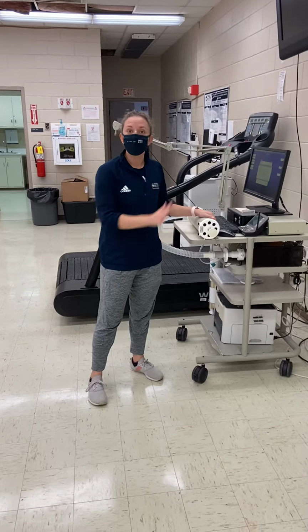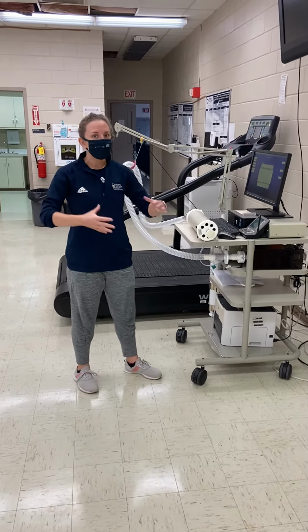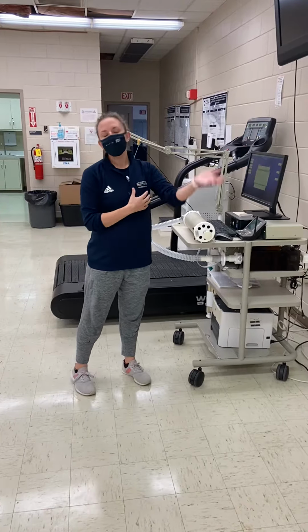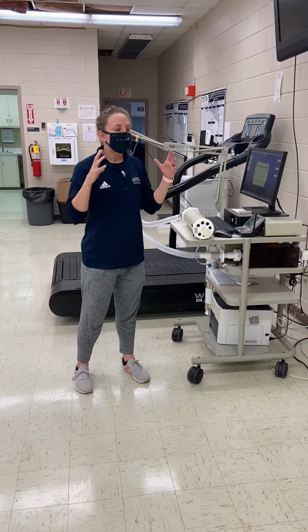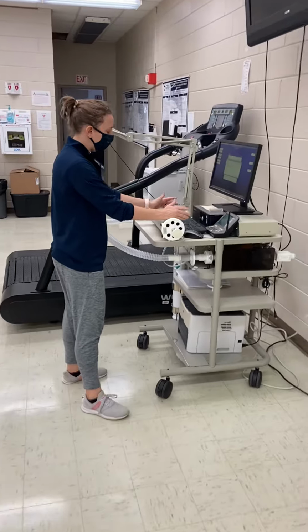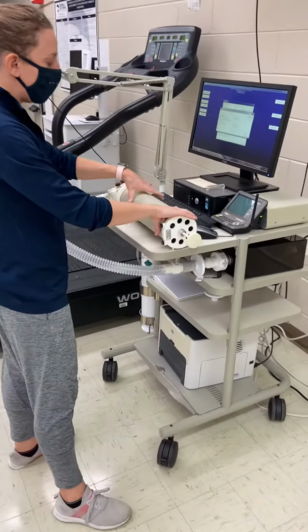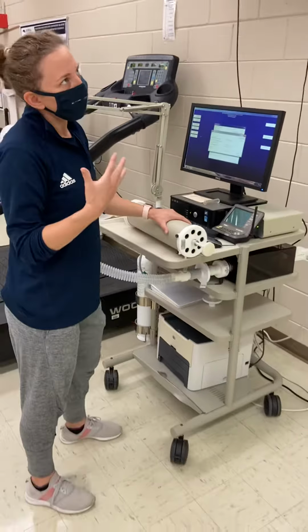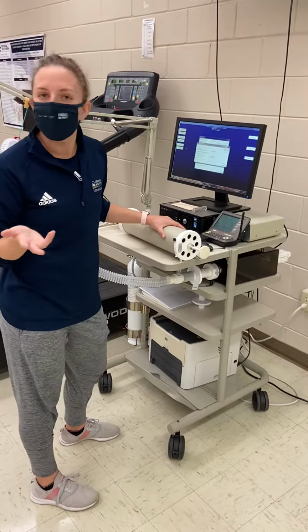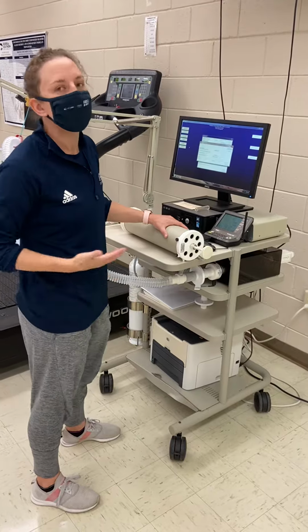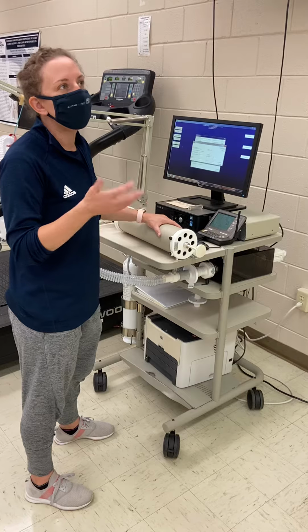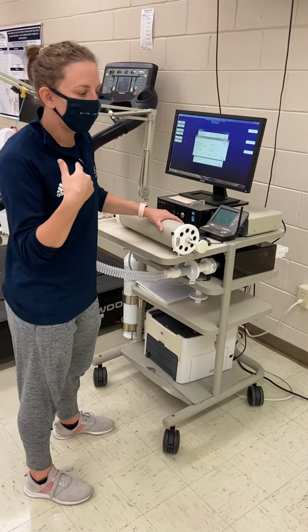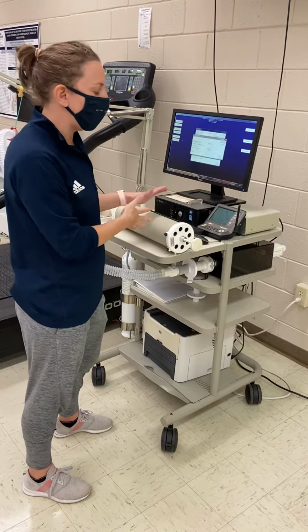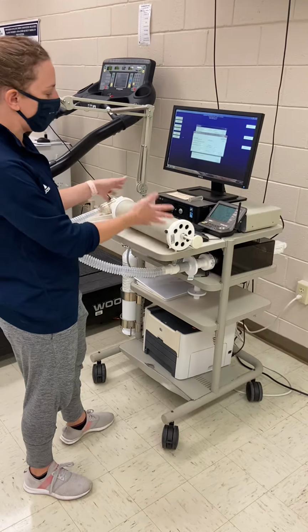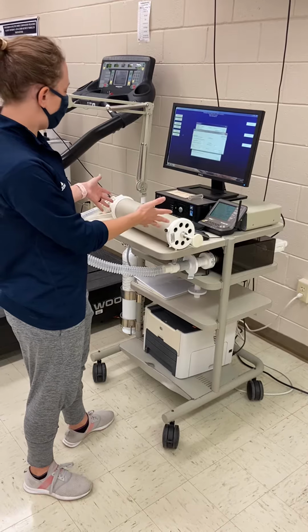Right, so the second step of calibration is a flow meter calibration, because it's one thing to know the amount of oxygen, or the volume of oxygen, the volume of carbon dioxide, but we're measuring that while someone is breathing. So we have this calibration syringe here that is 3 liters. So it's roughly the average lung volume of a person regardless of sex. Obviously, depending upon if they're really tall, male, or shorter, it could be more or less than 3 liters, but this is a pretty good reflection of lung volume here.